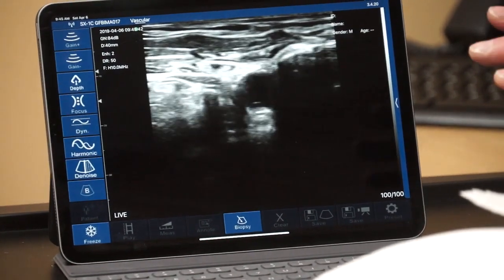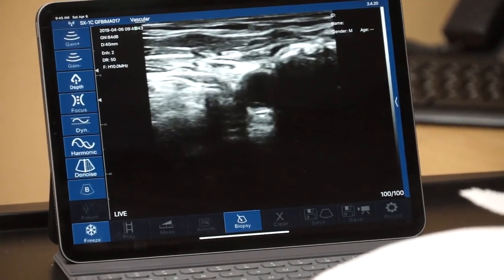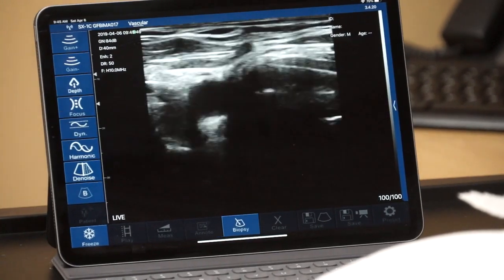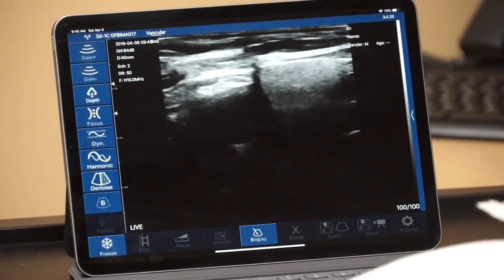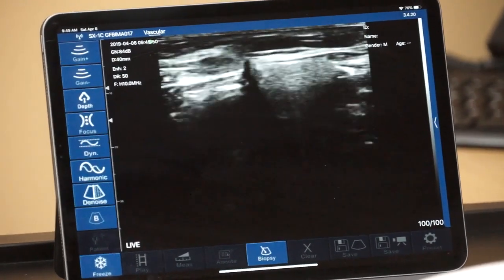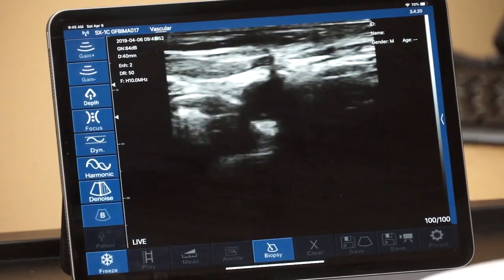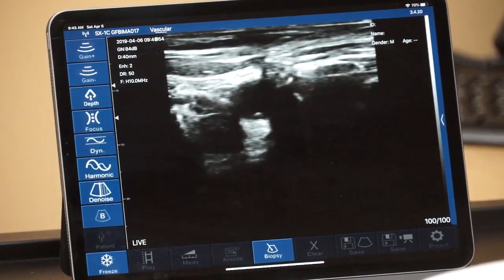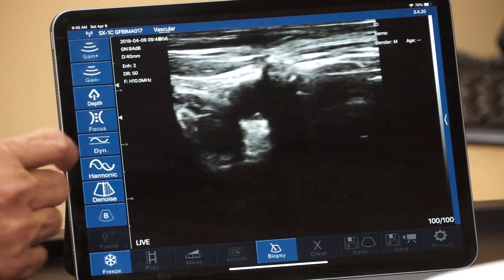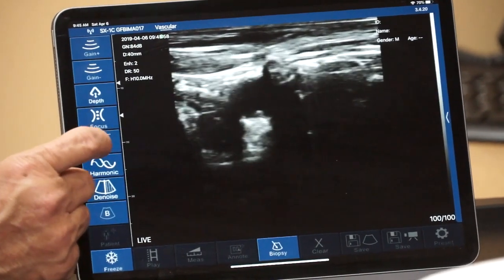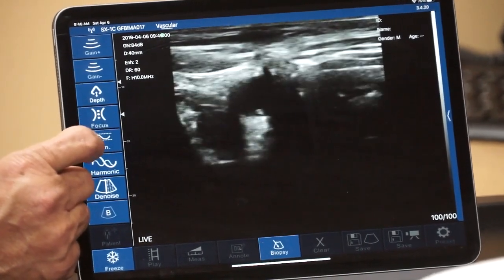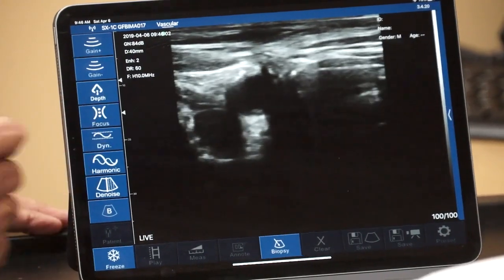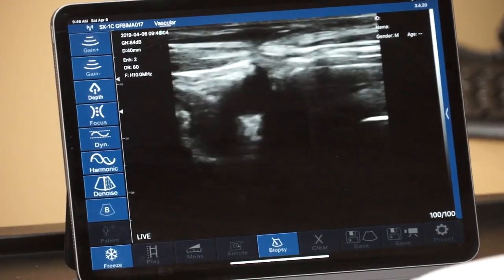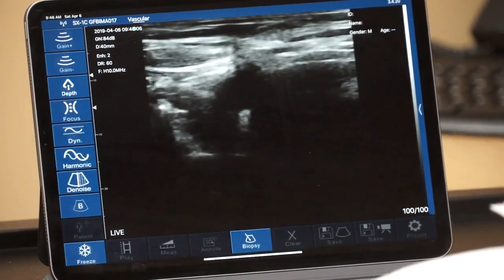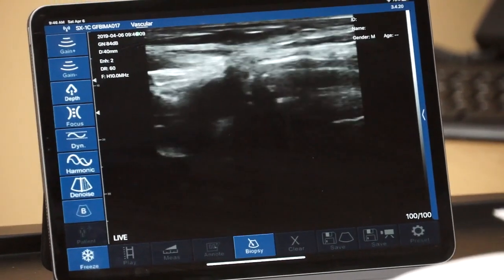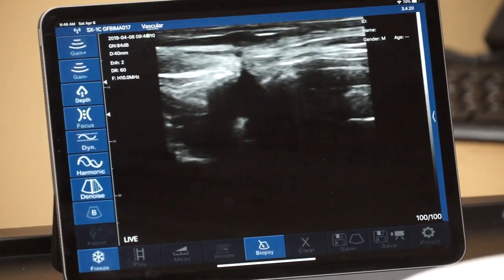Now, this is the lower end. This is at 50, and you can see very clearly that the image is quite bright and pretty heavily speckled. It looks like someone put pepper on our screen. So we're going to move that up now just a little bit at a time from 50, and we'll watch the image change. That's good there, I think. At that point, our image has become a little softer. We're able to see the structures a little more clearly without the bright reflectance.